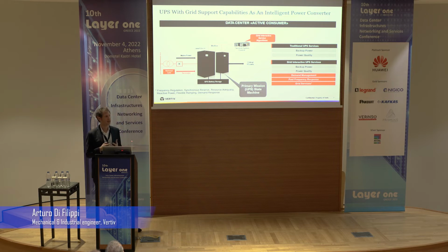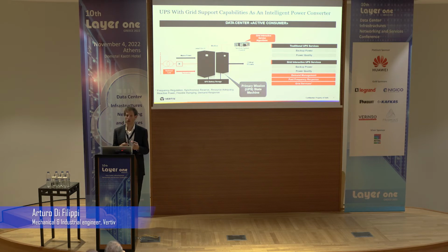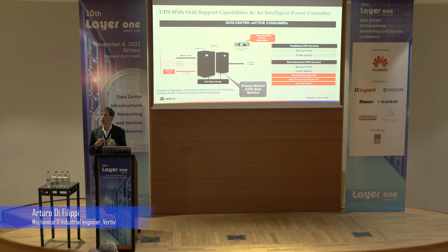And traditionally the UPS has, since many years, the function to improve the power quality because of double conversion, and to provide backup power. So there's a grid outage, the UPS is required to go, and the batteries that are associated with the UPS are basically used only when there is a grid outage. And the rest of the day, the rest of the year, they are sitting there, they are not getting discharged. Of course, you are not consuming the batteries, but at the same time, and this is what we are trying to pass as message, you are kind of wasting some opportunities that you could have in this scenario.